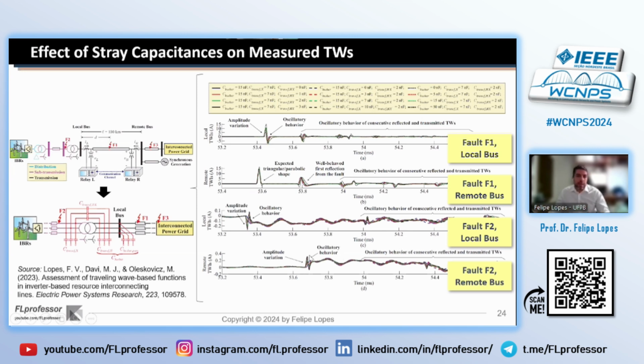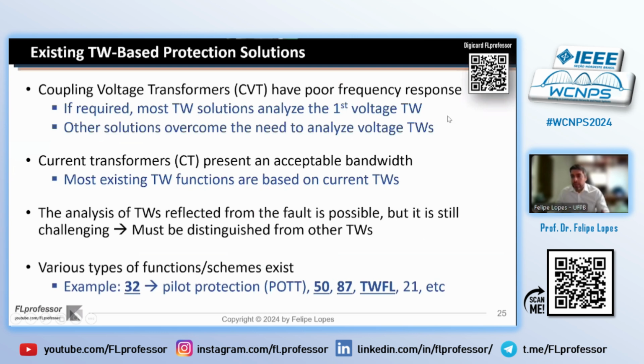And there is an important aspect that I have to point out here as well: when a fault takes place behind the transformer here at point F2, the stray capacitances in between the transformer windings are very small, in such a way that only very attenuated traveling waves are measured at both ends. So we measure a very attenuated wavefront here on the local bus, and then a very attenuated traveling wave also on the remote bus. As a consequence, this principle has been used to implement some new protection functions based on traveling waves, as I will explain later on. So, some remarks about existing traveling wave protection solutions.